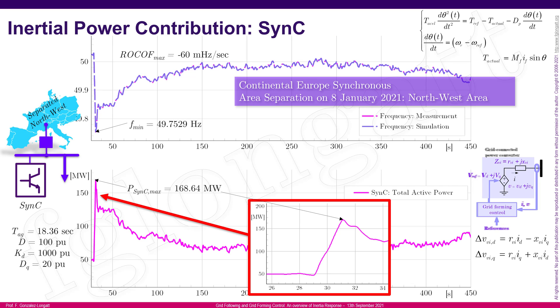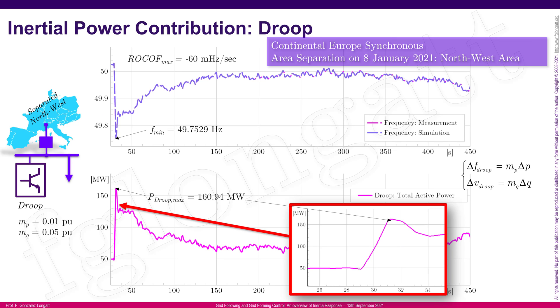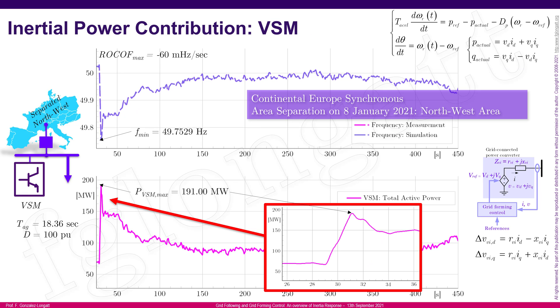The Synchronverter provided 168 MW of inertia power contribution during the under-frequency event. The droop control, following a linear relationship between active power and frequency deviation, reached approximately 160 MW in a near-linear fashion. The virtual synchronous machine (VSM), which controls the internal rotational speed using active power deviation (ΔP), delivered the highest contribution at 191 MW.